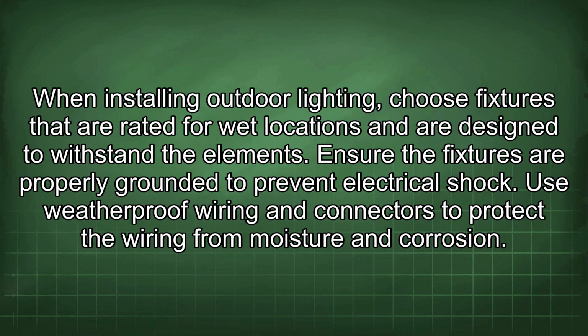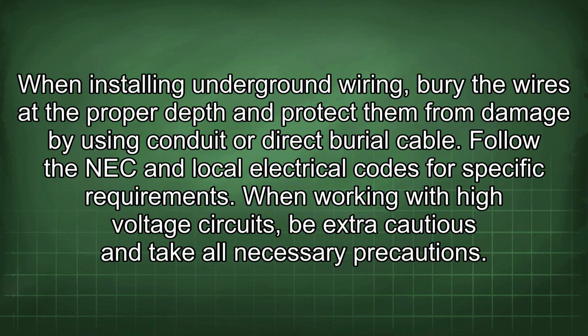When installing outdoor lighting, choose fixtures that are rated for wet locations and are designed to withstand the elements. Ensure the fixtures are properly grounded to prevent electrical shock. Use weatherproof wiring and connectors to protect the wiring from moisture and corrosion. When installing underground wiring, bury the wires at the proper depth and protect them from damage by using conduit or direct burial cable. Follow the NEC and local electrical codes for specific requirements.